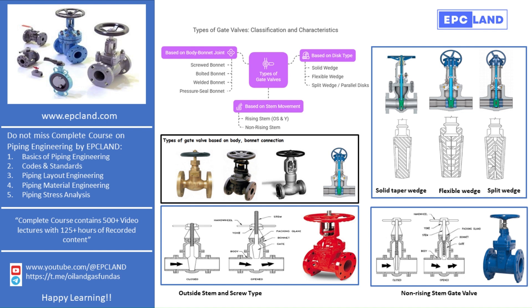Now let's move to the second classification: types of body and bonnet joints. This classification is based on how the valve body is connected to its top part called the bonnet. The screwed bonnet is the most basic design, used in low-cost valves where high pressure or temperature is not a concern. The bolted bonnet is the most commonly used design. A gasket is used between the body and the bonnet to ensure tight sealing, and this design is easy to disassemble for maintenance.